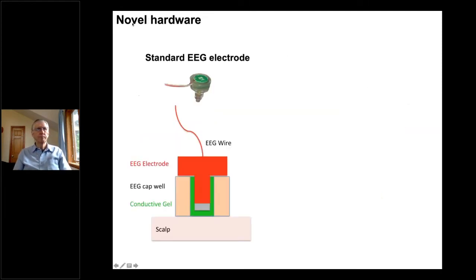Now, the way that we went about this was essentially coming up with some new hardware. Standard EEG, this is an example of Active2 BioSemi electrode, relatively small. This is obviously zoomed in. Now the side profile view of this, you can imagine if this is the scalp of a human or of the dental plaster phantom, you have the electrode well, you inject some gel over there, insert the electrode, you're then recording the voltages from here, and the wires run out.